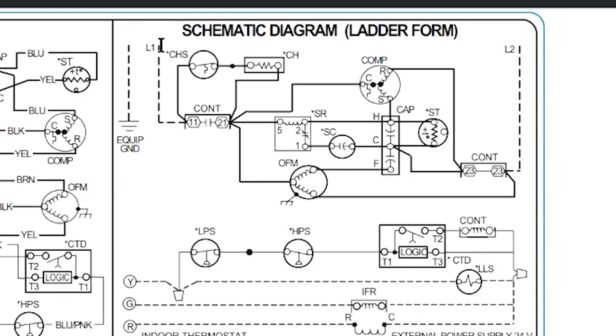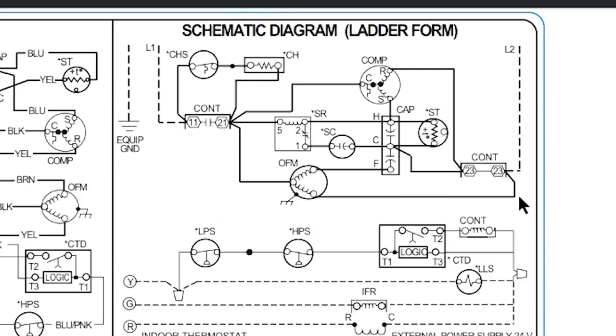The dashed lines mean we installed those wires. An equipment ground is always shown as little lines making an inverted pyramid. We've got L1, a compressor contact — and notice it's not connected to the rest of the contactor, it's just out by itself. Down here is the 24-volt side of the circuit, coming from a separate external power supply — 24 volts from the air handler. This is a condenser diagram.